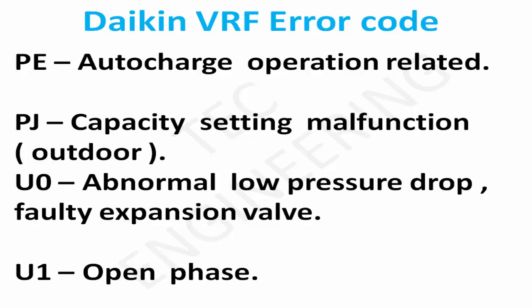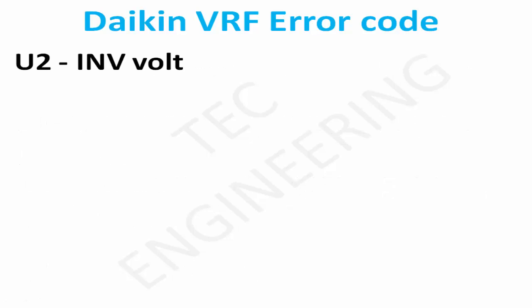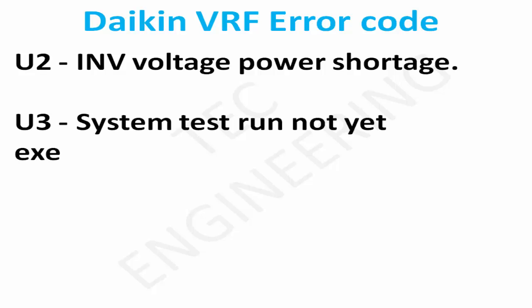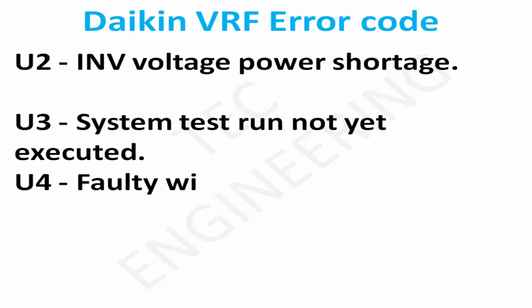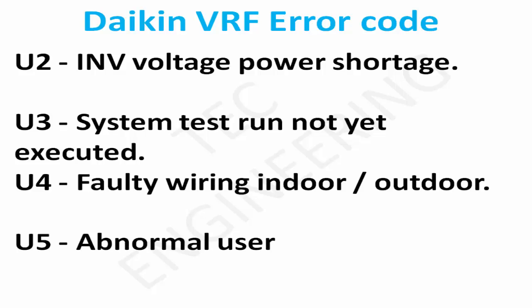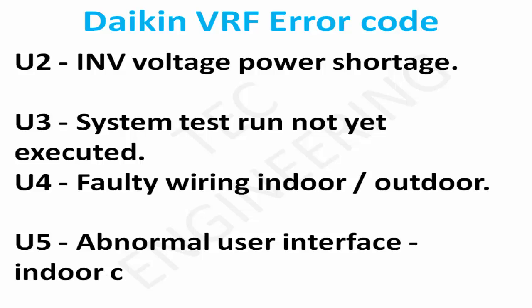PE: Auto charge operation related. PJ: Capacity setting malfunction, outdoor. U0: Abnormal low pressure drop, electronic expansion valve. U1: Open phase. U2: INV voltage power shortage. U3: System test run not yet executed. U4: Faulty wiring indoor-outdoor. U5: Abnormal user interface indoor communication.